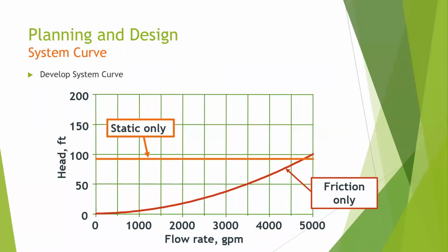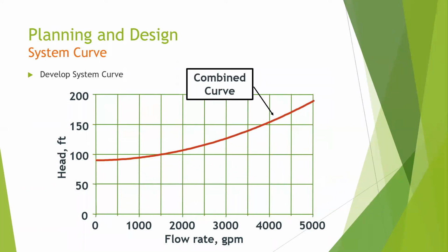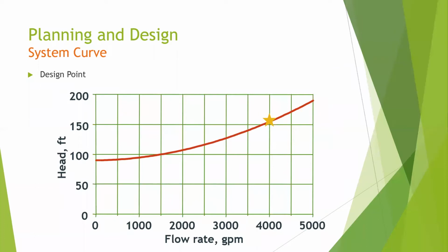Once a firm station capacity has been determined, a system curve is calculated. The curve is a combination of static lift and friction loss through piping and valves. Results are combined in the pump station system curve. Just like that. This system curve will tell us the pressure required to meet a certain flow rate. In this example, a station firm capacity is 4,000 GPM. Pumps will need to produce around 160 foot of head to meet the capacity.